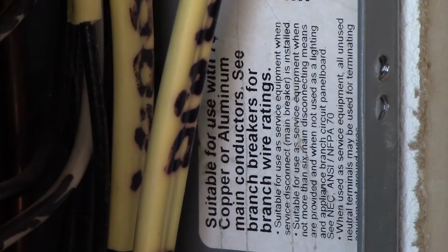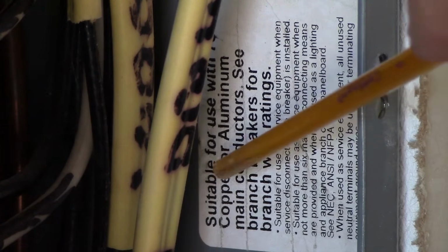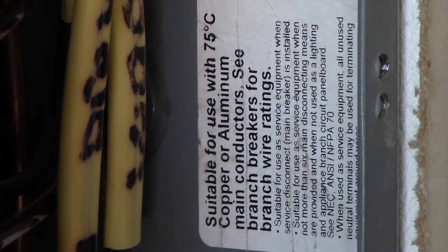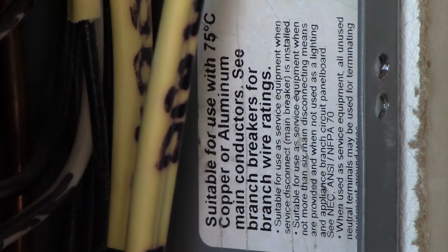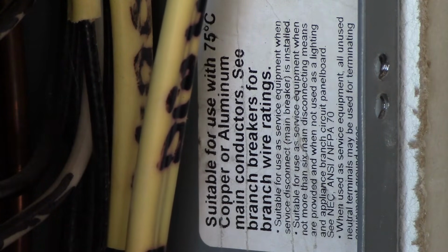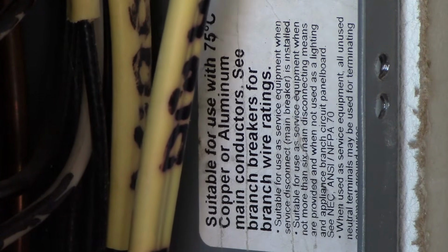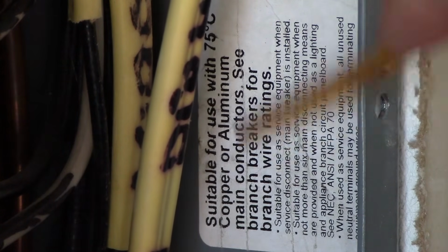Now, here we are at the other label on the right side of this cabinet. Here's what we got to earlier. It says suitable for use with 75 degrees C copper or aluminum main conductors. So again, the conductors coming in are rated at 75 degrees C, even though we know all of these non-metallic sheath cables are rated at 60 degrees C for their application as far as ampacity. Now, we can use the 90 degree ampacity value for adjustment and corrections on non-metallic sheathed cable when they're running in insulation, or for the number of current carrying conductors or bundling and what have you, found in the requirements of 334.80. But as a general rule, they're limited to the 60 degree column of 310.15(B)(16) when it comes to ampacities. But the 75 applies to the main conductors.